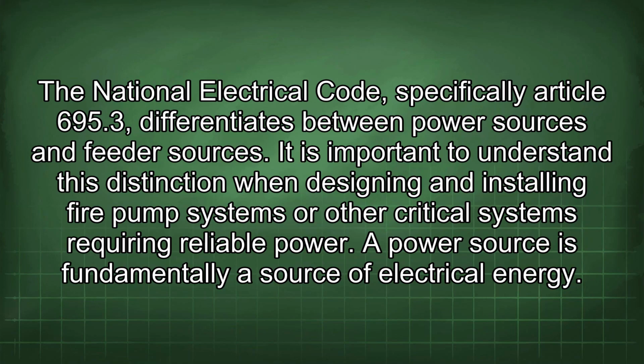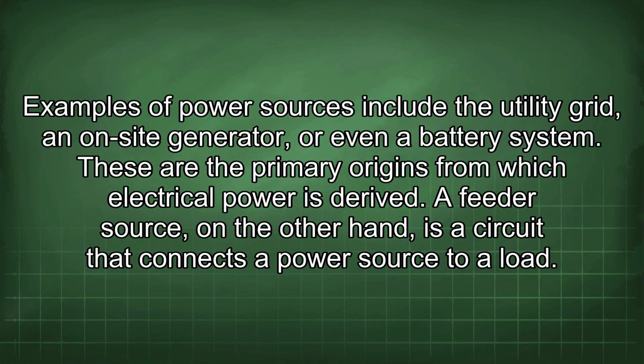The National Electrical Code, specifically Article 695.3, differentiates between power sources and feeder sources. It is important to understand this distinction when designing and installing fire pump systems or other critical systems requiring reliable power. A power source is fundamentally a source of electrical energy. Examples of power sources include the utility grid, an on-site generator, or even a battery system. These are the primary origins from which electrical power is derived.